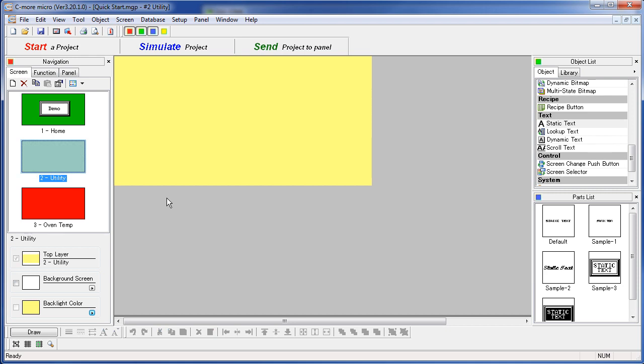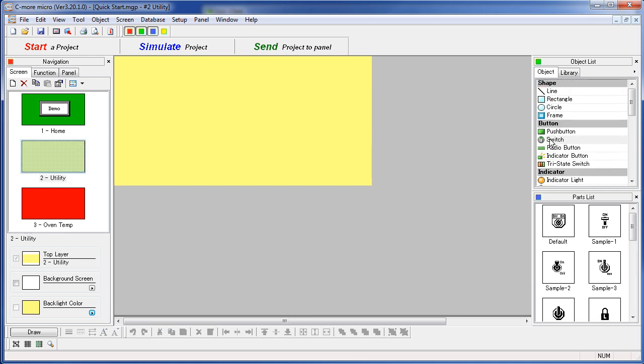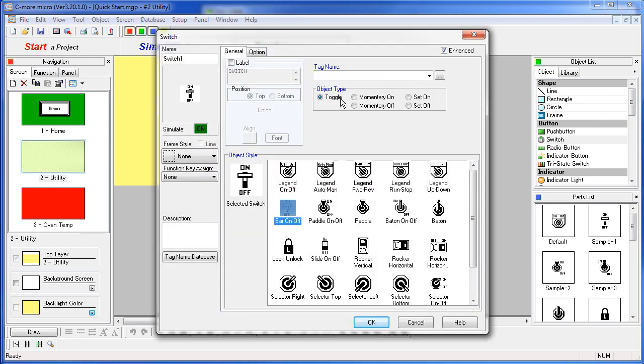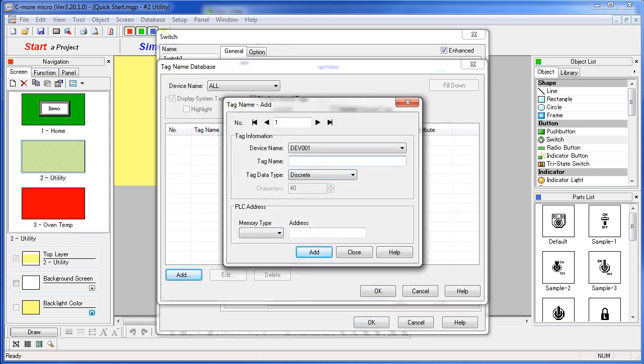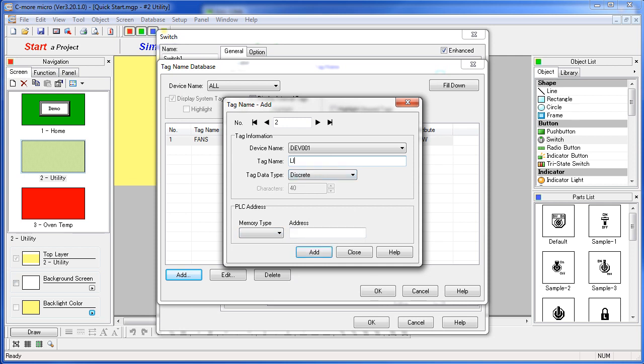Screen 2 is our utility control screen. We will add a bar switch here to control the fan tag. We haven't created any tags yet so we click on this button. Add a tag – call it the fans tag. This will be a discrete tag located at memory address C100 on the Click PLC. We also need a lights tag, so let's add that in – it will also be a discrete at address C101 on the Click PLC.